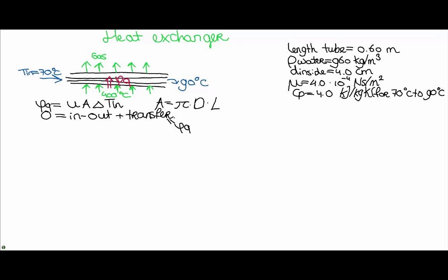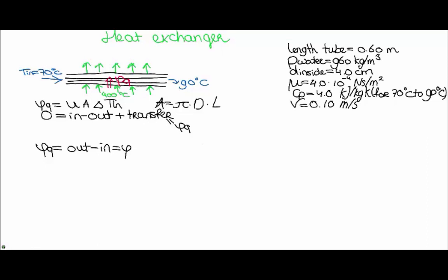So if we write this another way, we get Phi q equals out minus in, which is the mass flow of the water times the heat capacity of the water times T out minus T in. If we fill in the equation for the heat transfer, we get: U times A times delta T ln equals the mass flow of the water times the heat capacity of the water times T out minus T in.